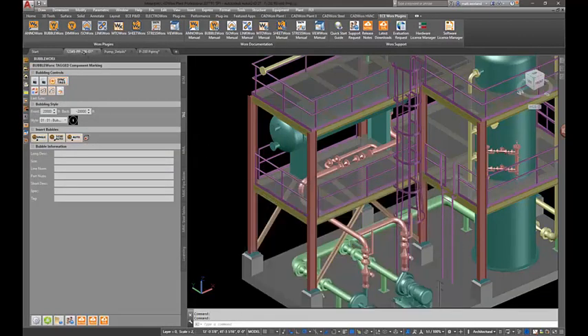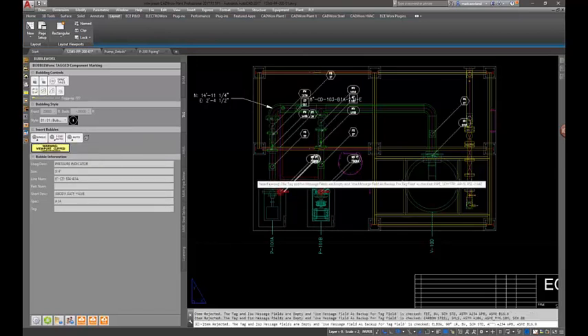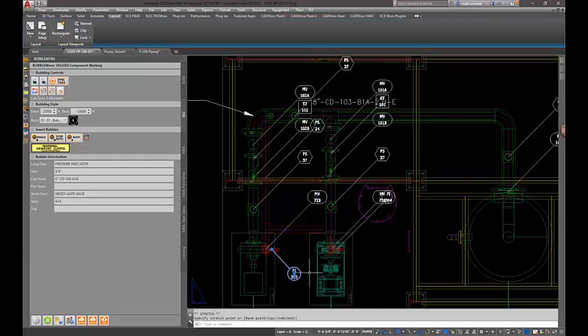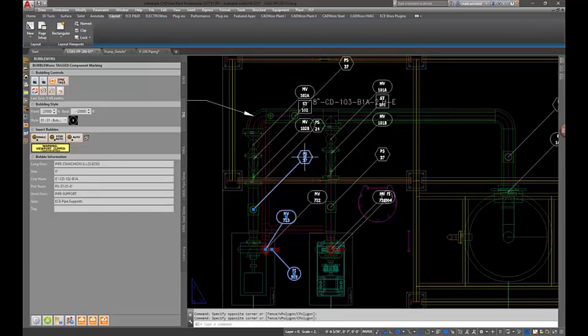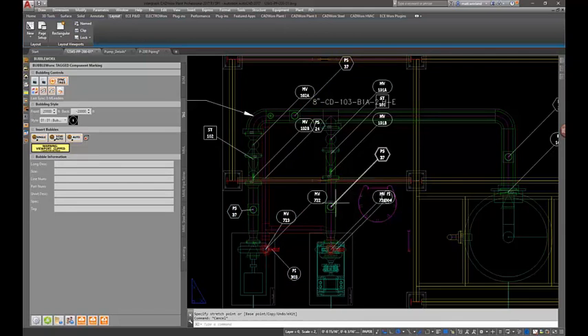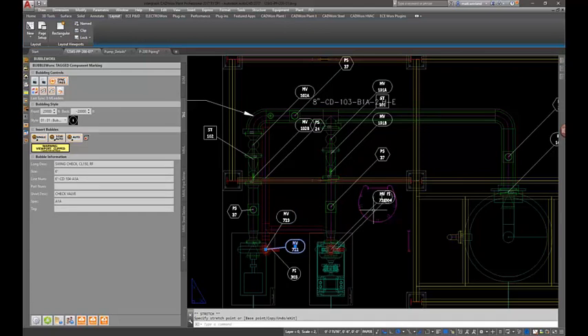If you fill that information out, we can automate the entire process. It looks at this information and compares it to the current component — if the component uses a different style, we automatically get a different style bubble. So all instrumentation and control valves come in with a circle, manual valves come in with a rounded shape, pipe supports with a pointed or rectangular shape, and specialty items like strainers use a rectangle. It's pretty quick and powerful to go through and pick what type of annotation you want for each component.